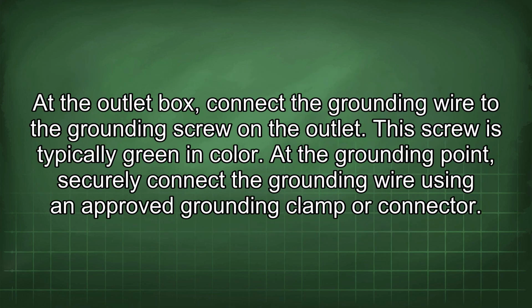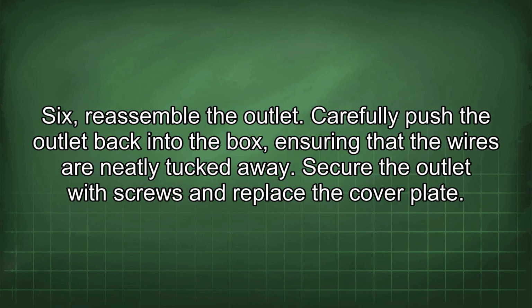5. Connect the grounding wire. At the outlet box, connect the grounding wire to the grounding screw in the outlet. This screw is typically green in color. At the grounding point, securely connect the grounding wire using an approved grounding clamp or connector. 6. Reassemble the outlet. Carefully push the outlet back into the box, ensuring that the wires are neatly tucked away. Secure the outlet with screws and replace the cover plate.